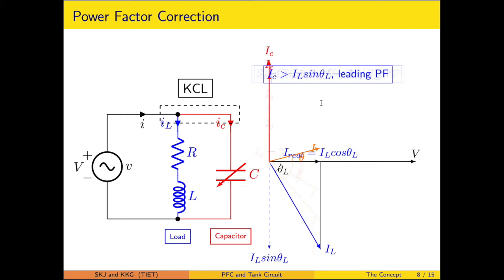So this power factor correction we studied for different cases. The power factor correction is achieved by varying the compensation level, and the compensator is placed parallel to the industrial load. Now the one point to be highlighted is that the load is taken here as inductive, so the compensator is of capacitive nature. If the load somehow comes out to be of capacitive nature, then the compensator has to be of inductive nature likewise.